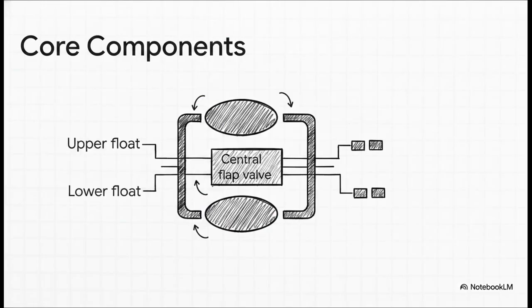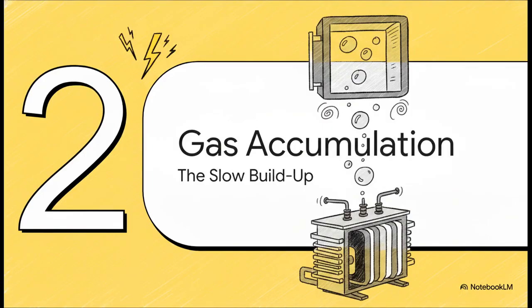Here is the absolutely crucial point. These internal components, the floats and the flap, physically move in response to changes in the fluid. And when they move, they do something incredibly important. They activate connected reed-type switches. These are basically simple magnetic switches. They bridge the gap between mechanical movement and electrical communication, sending a signal straight to the electrical controller and monitoring circuit of the transformer.